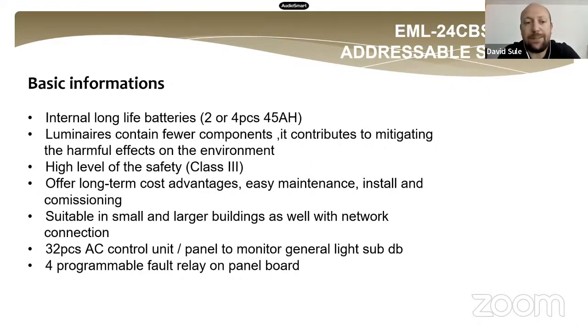Because it's a DC 24 volt system, you should use a 2.5 diameter cable, because the lowest voltage which is enough for the lights is 21 volts. So we have a calculation help table for the designers to calculate the maximum length of the cable and the maximum load per line, and it calculates how many panels you need in one system if you give the quantity of the lights.